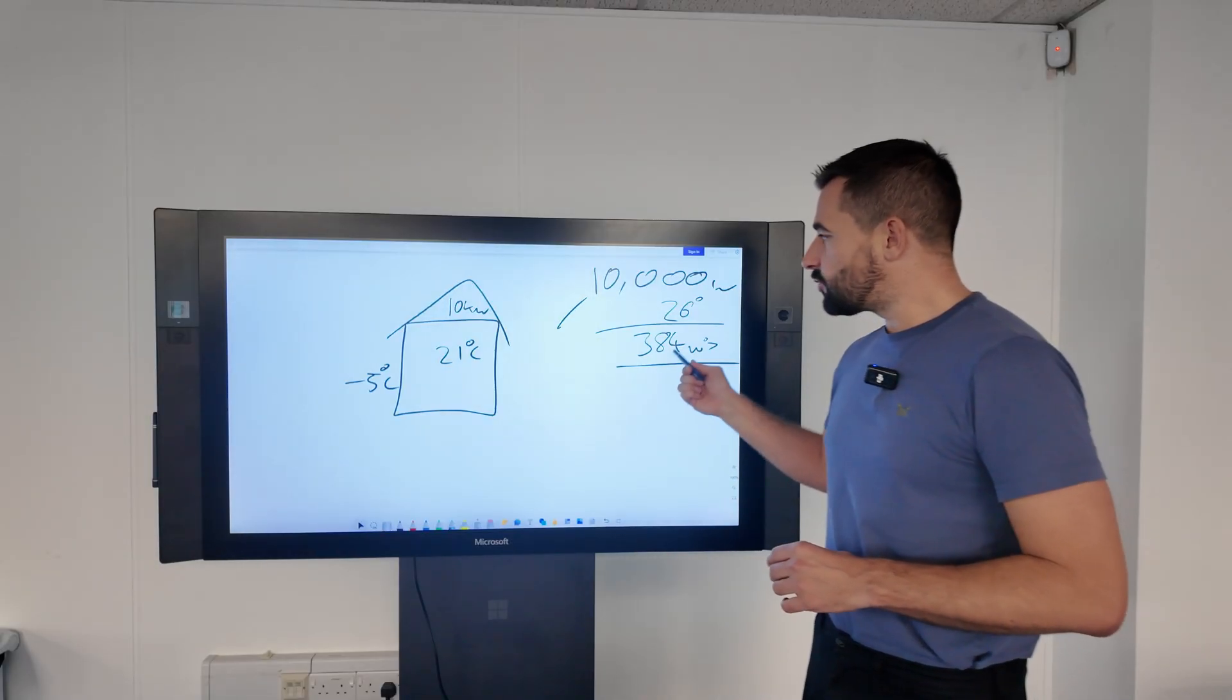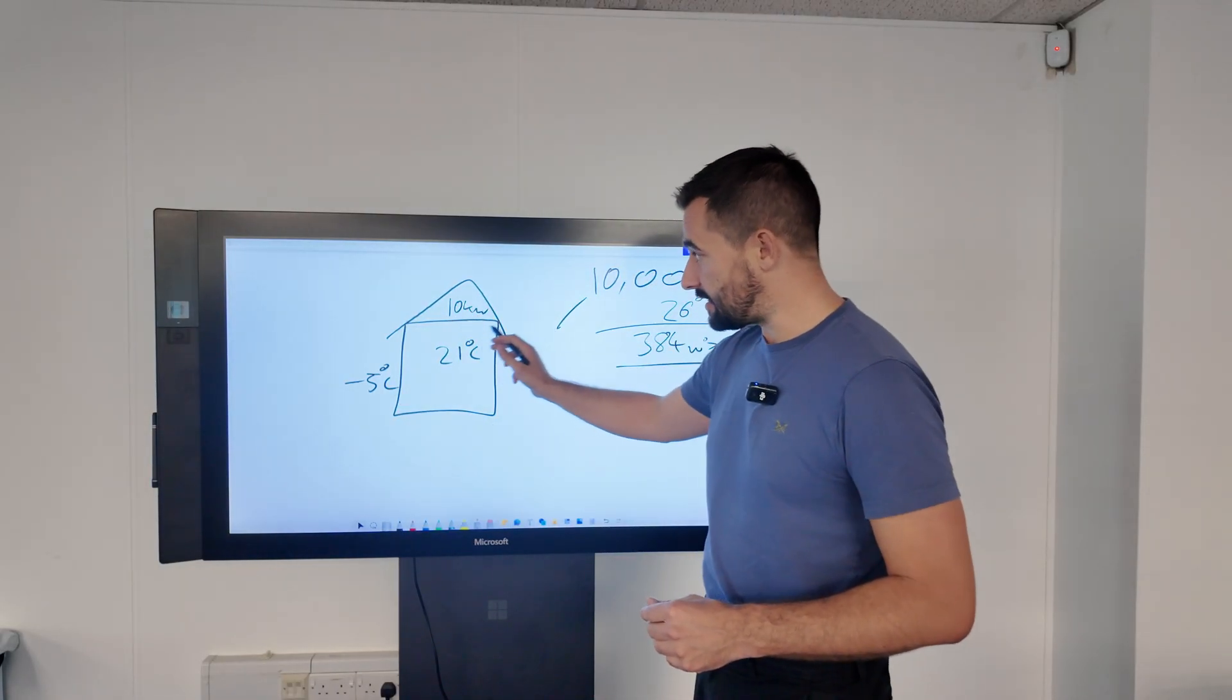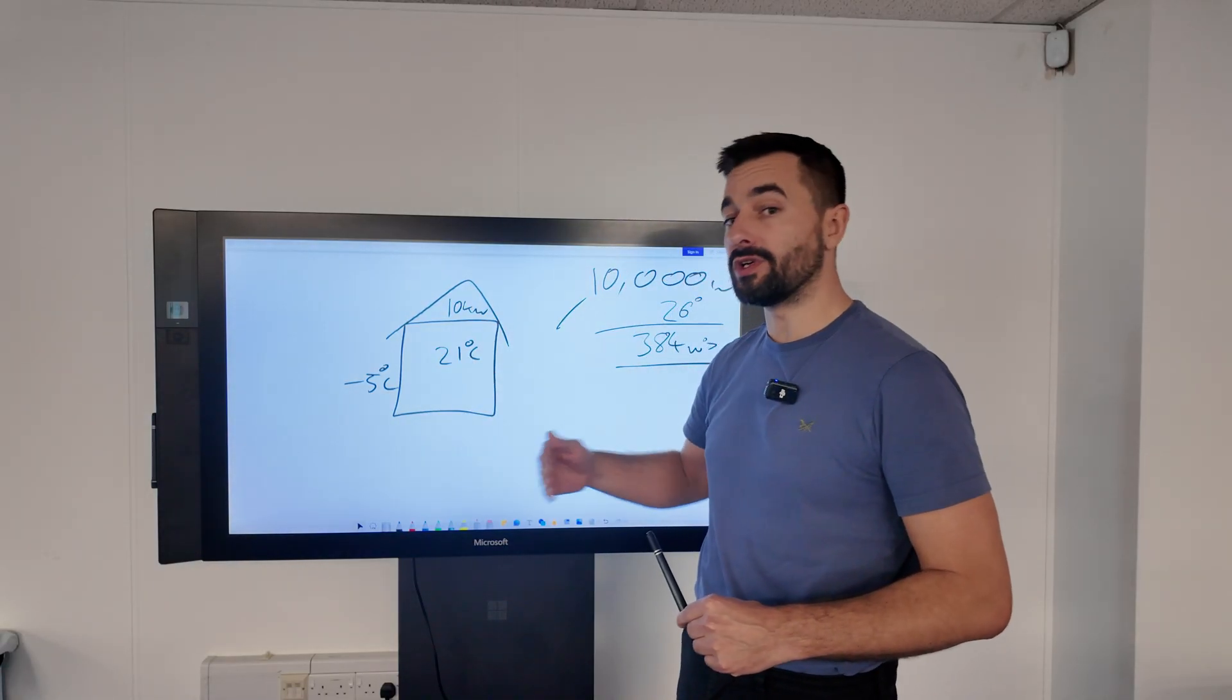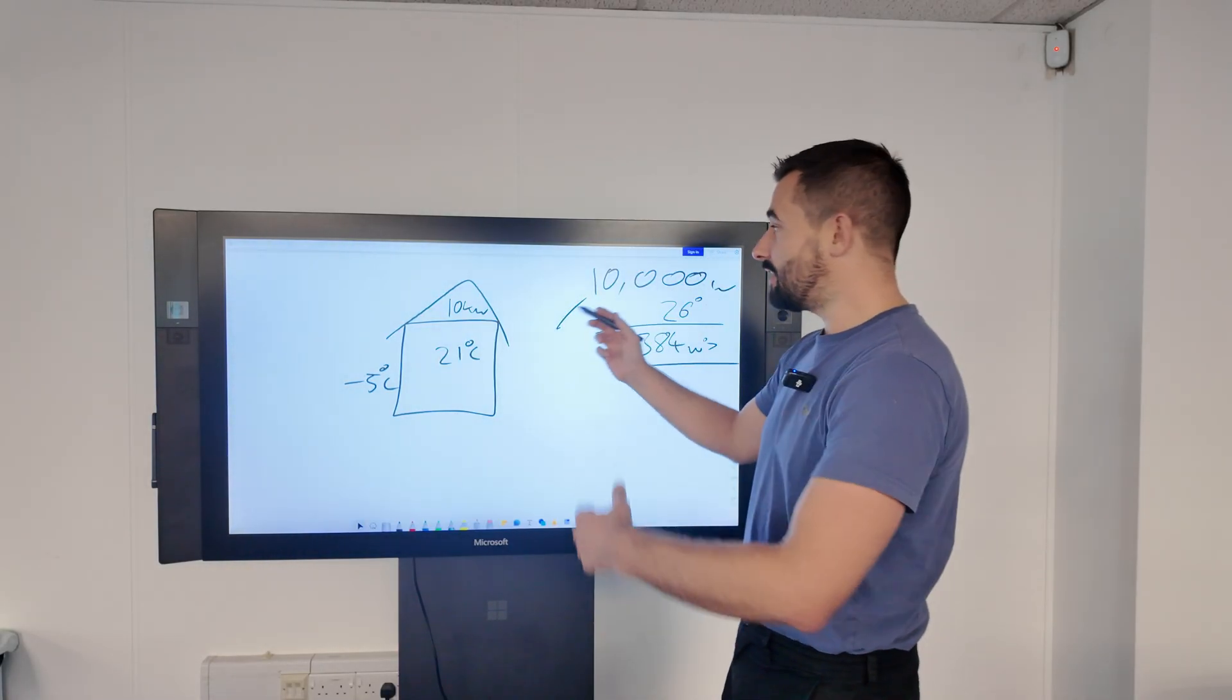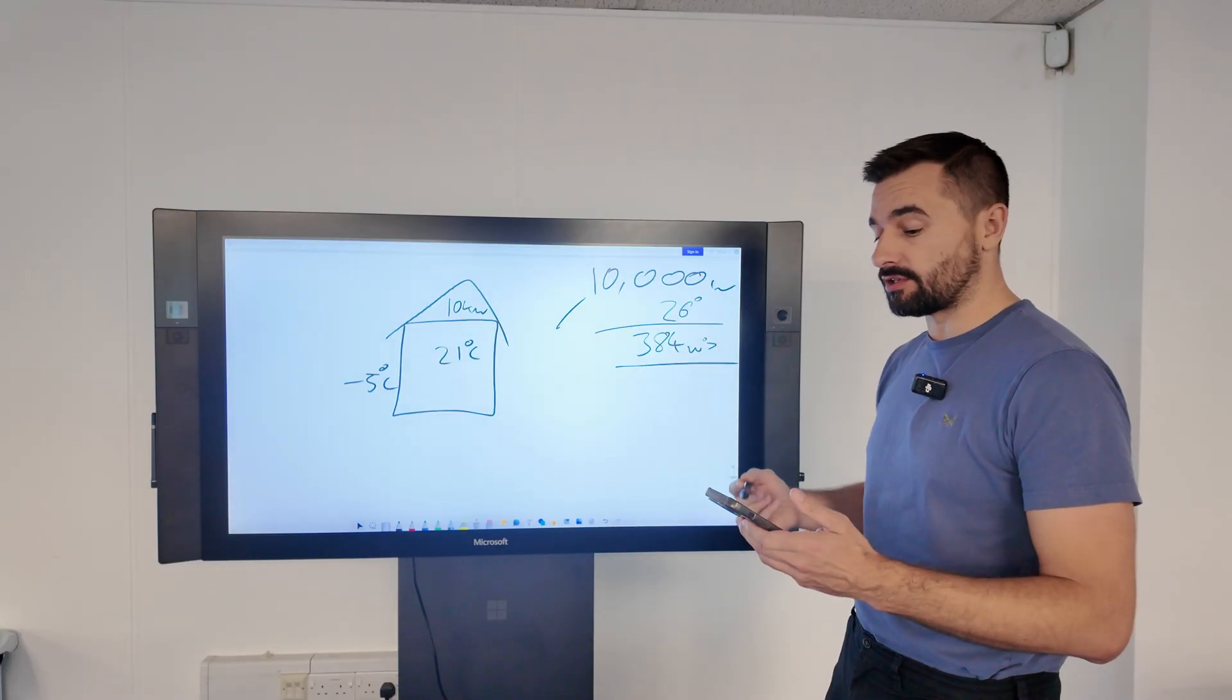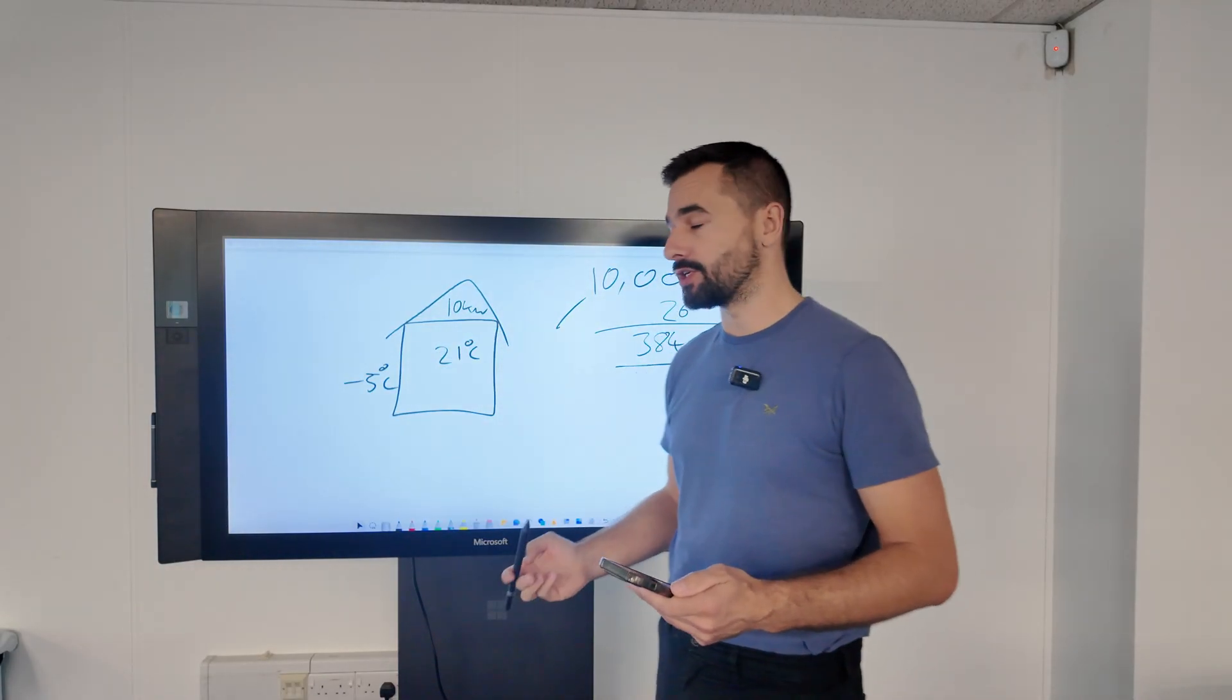Now we're armed with this information. That gives us the ability to calculate the heat loss at any given outdoor condition. So just to cover that again, the original heat loss is 10 kilowatts when we have a 21 degree room temperature at minus 5 degrees outdoor temperature. We're lifting the temperature from minus 5 to 21, which is 26 degrees lift. We calculated the heat loss at 10 kilowatt, which is 10,000 watts. If we divide that wattage by the differential between those two temperatures, that will give us our watts per degree rise. Just slow that down in your head, think about it until you understand that bit.